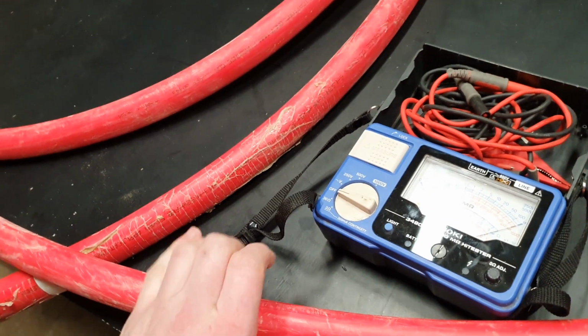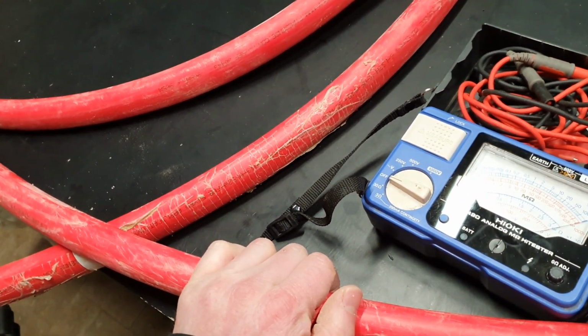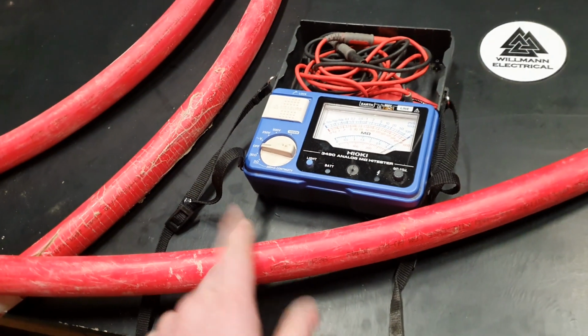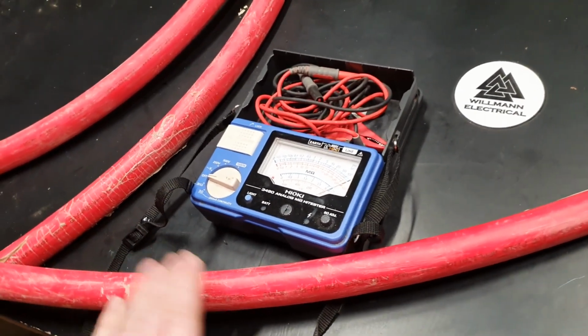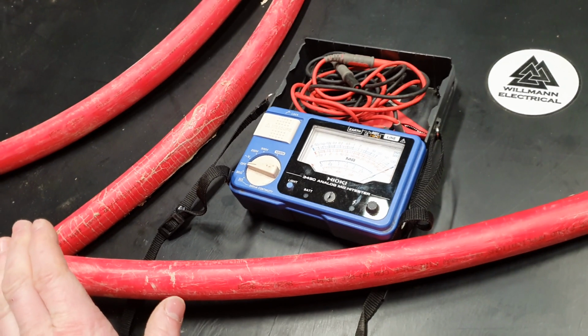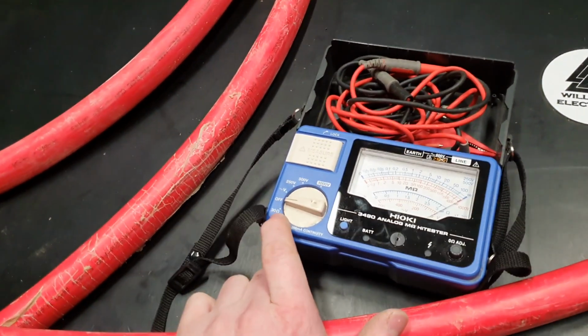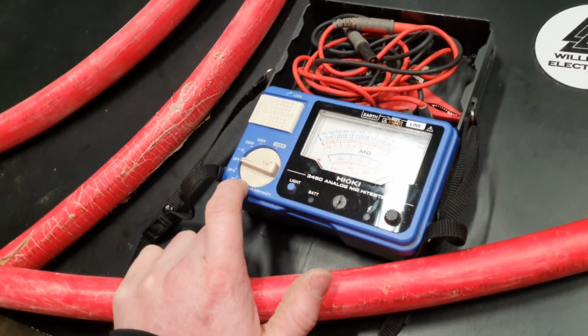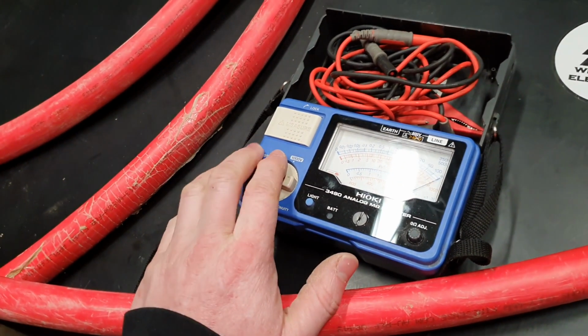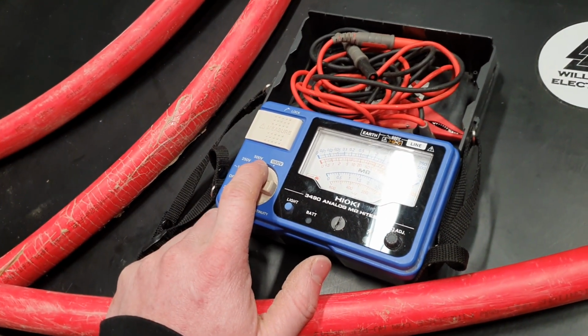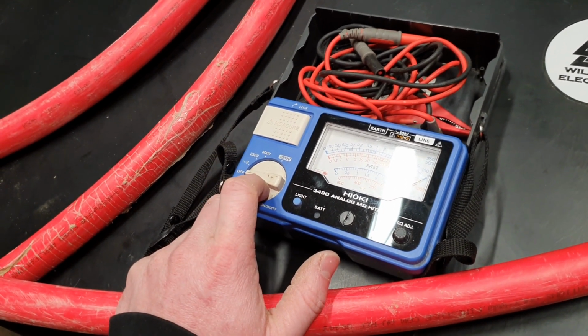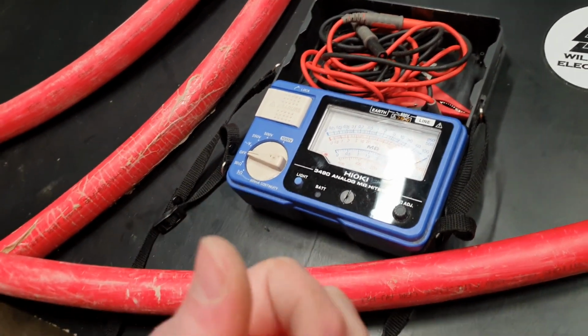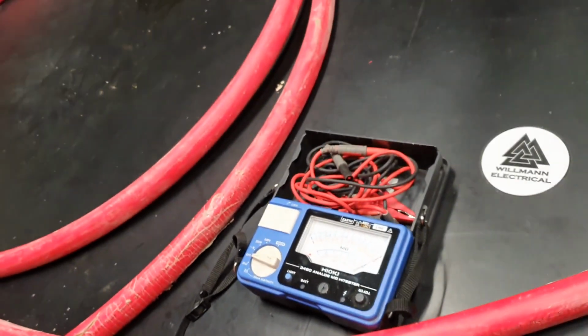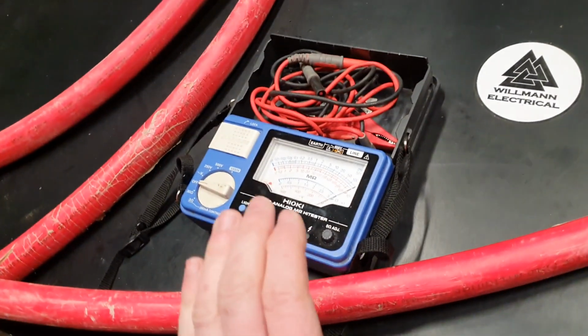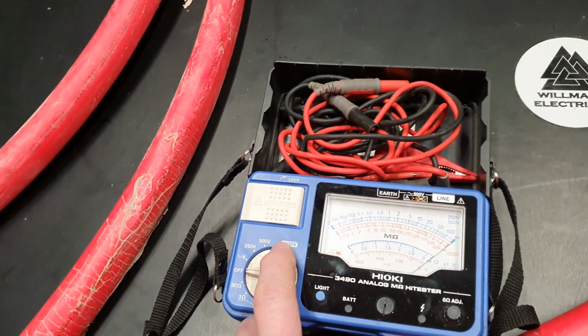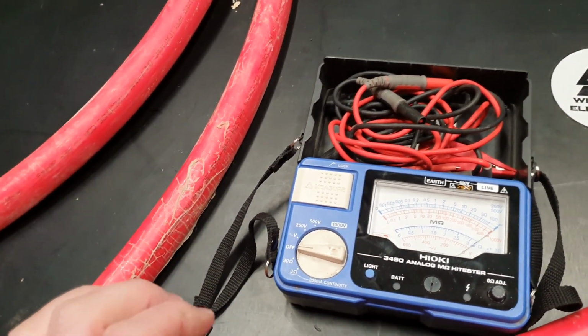I might have to wet the cable to help me out. Between the earth stake and this cable I was getting 0.8 of a megaohm. It was completely open circuit on the resistance check, exactly how it's supposed to be. But with insulation resistance testing, you need to put some voltage down the cable and pressure test it. If you don't understand this sort of stuff, it's like a pressure test on a cable - you need to apply pressure to find the weak points.